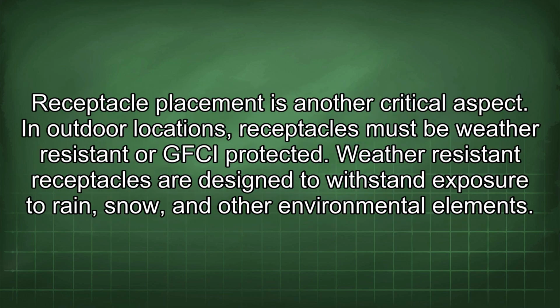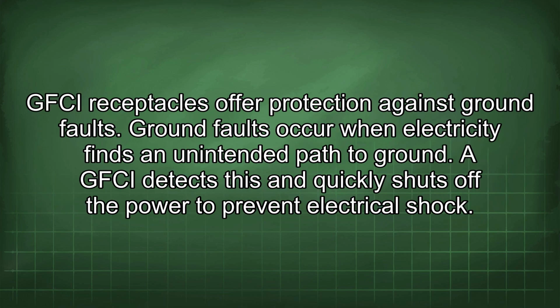Receptacle placement is another critical aspect. In outdoor locations, receptacles must be weather-resistant or GFCI protected. Weather-resistant receptacles are designed to withstand exposure to rain, snow, and other environmental elements. GFCI receptacles offer protection against ground faults. Ground faults occur when electricity finds an unintended path to ground. A GFCI detects this and quickly shuts off the power to prevent electrical shock.